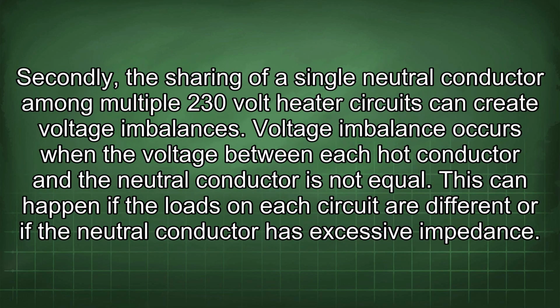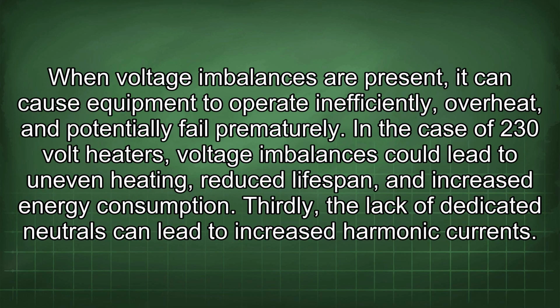Secondly, the sharing of a single neutral conductor among multiple 230-volt heater circuits can create voltage imbalances. Voltage imbalance occurs when the voltage between each hot conductor and the neutral conductor is not equal. This can happen if the loads on each circuit are different or if the neutral conductor has excessive impedance. When voltage imbalances are present, it can cause equipment to operate inefficiently, overheat, and potentially fail prematurely. In the case of 230-volt heaters, voltage imbalances could lead to uneven heating, reduced lifespan, and increased energy consumption.